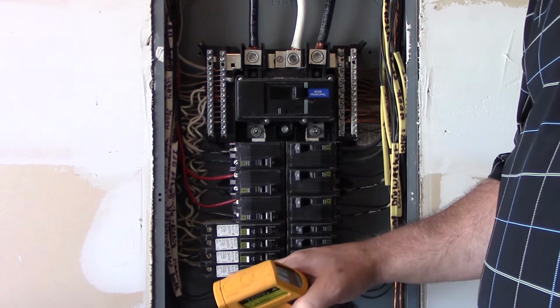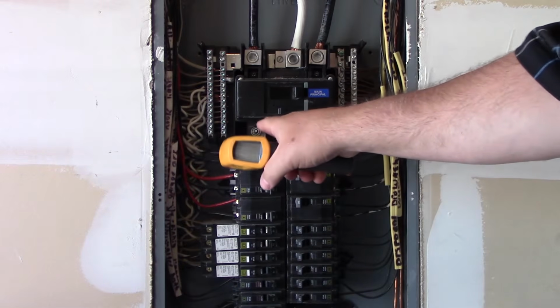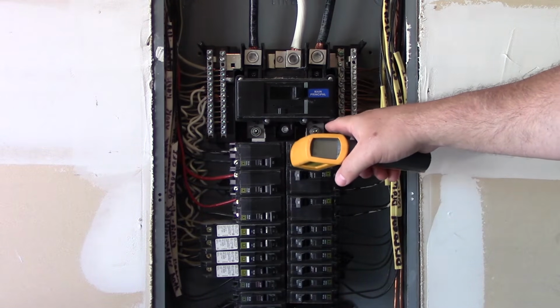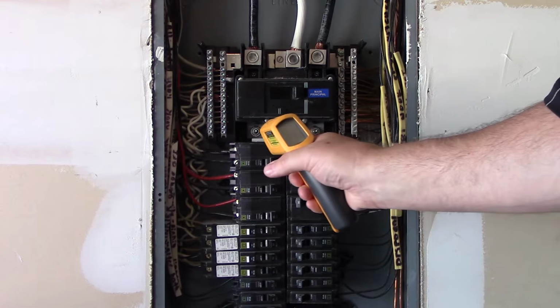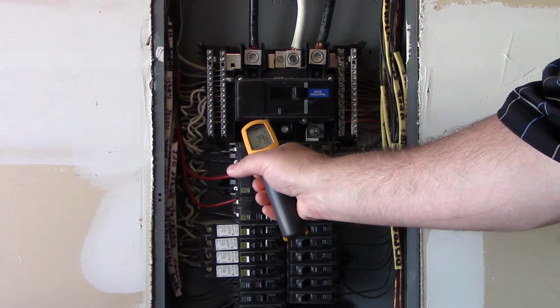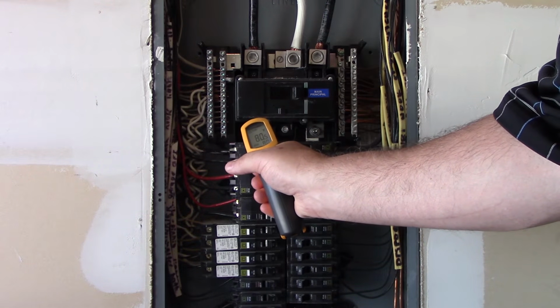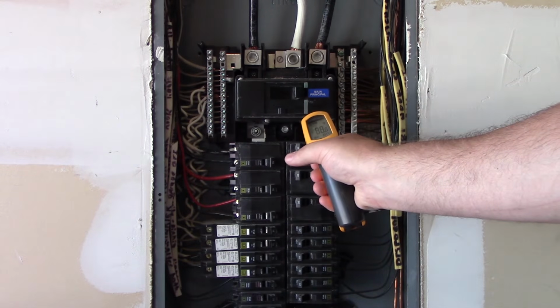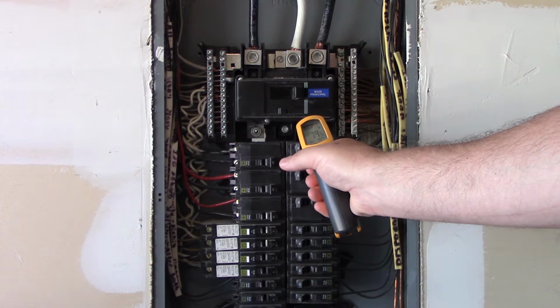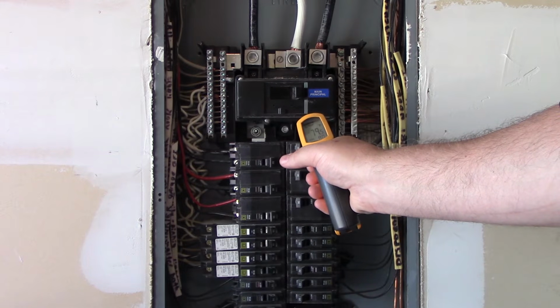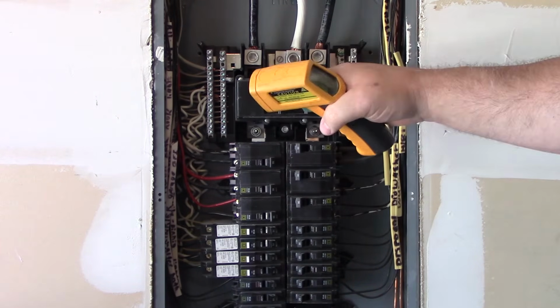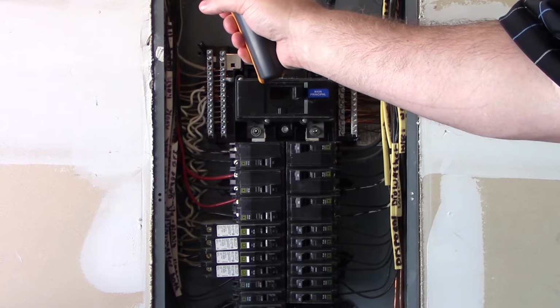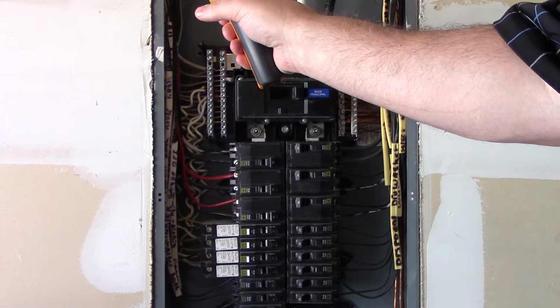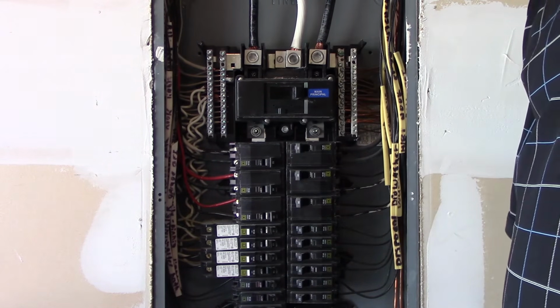Now I'm going to do each one of these breaker terminals. I'm also going to shoot, in here you can actually see the terminal, the bus on the panel board. I'm going to shoot it and see what I get here. That should be about the same, so it's about 80. Then I'm going to shoot over here, and it's about 79.5 or 80. So I'm feeling pretty consistent here. Nothing out of the ordinary. The ambient in here, like I said, when I shoot the actual cabinet, is about 80. So everything else looks pretty good.